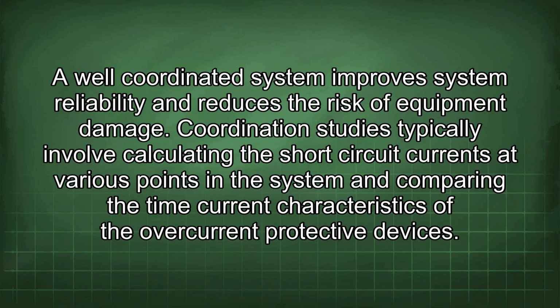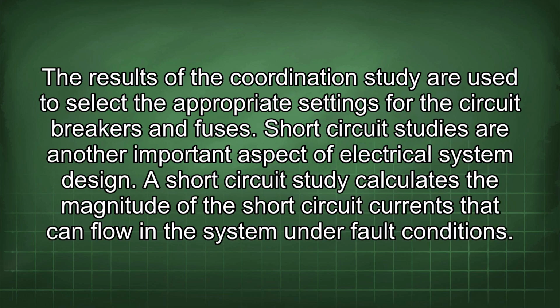Coordination studies typically involve calculating the short-circuit currents at various points in the system and comparing the time current characteristics of the overcurrent protective devices. The results of the coordination study are used to select the appropriate settings for the circuit breakers and fuses.